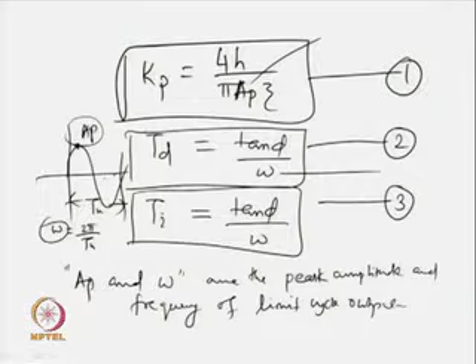So, these are the three explicit expressions we have for the parameters of the PID controller. And what are the unknowns we have in the right half of all these three explicit parameters of the PID controller? We have got ap and we have got ω. So, ap and ω are the peak amplitude and frequency of the limit cycle output. So, conduct the relay test, obtain the symmetrical output, measure this peak amplitude ap and measure the period Tu, which will give you ω equal to 2π by Tu. This is how you obtain the peak amplitude and frequency from the limit cycle output. Substitute in the 1, 2 and 3 and estimate the parameters of the PID controller. This is how tuning of PID controller, model free tuning of PID controller is done.